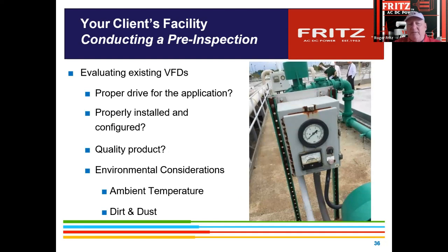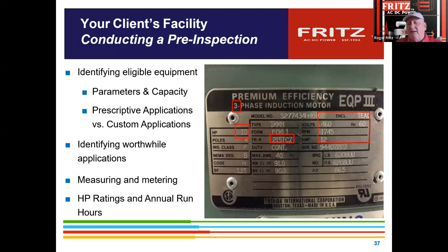Again, getting the compatibility correct to the motor is really key. We really recommend people take pictures of the nameplates so that a motor guy can look at it and see what its design was and what its amperage loads were. There have been application errors made because a 900 RPM motor at 100 horsepower has a different amperage rating than the same motor as an 1800 RPM motor. And you can't turn an 1800 RPM motor down to 900 RPM and get the same torque out. So it's important to understand the torque factors, especially in more constant torque loads.